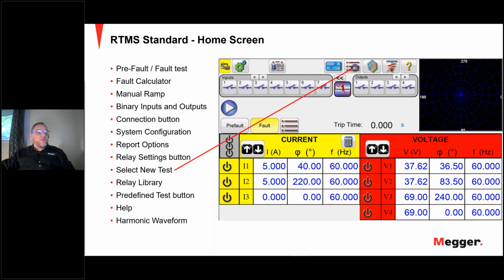In the select new test window, this is where the RTMS test menu is in two sections, for standard and enhanced, and more on this later in the presentation. We move on to the relay library, and this button provides access to the relay test plans from different relay manufacturers. Relay tests are performed in accordance with the relay manufacturer's specifications.